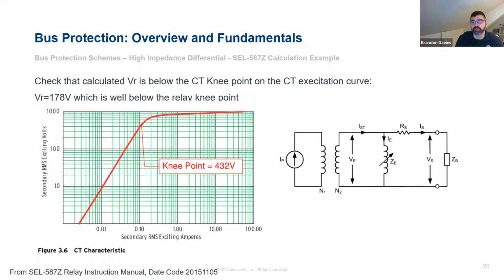And most relay manufacturers will provide some guidance on typical settings and typical ranges for how you go about configuring the relay to operate properly, because it's obviously in their best interest to have their customers have a lot of success with their relays because it makes them go out and buy more relays. So usually they provide some level of guidance on that, but in the end, it comes down to experience in the specific scenarios and the balancing act between all those factors of security and dependability and all those other protection system objectives. So great question.